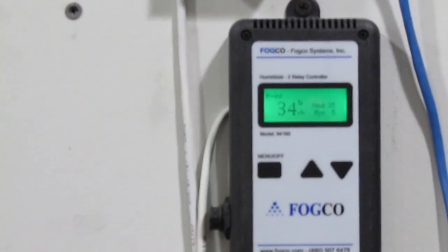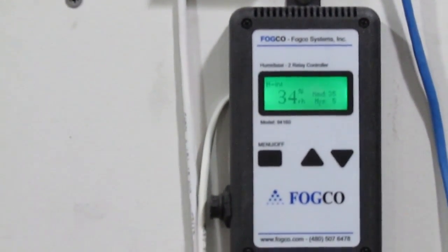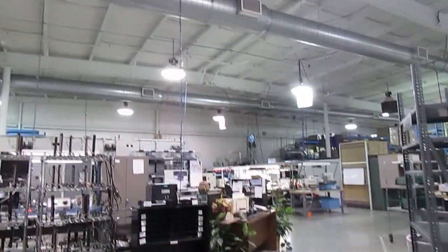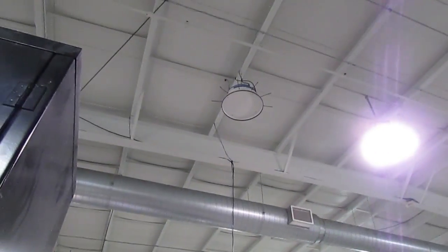The IPC standard is 30% to 70%. Here in western New York, where the winter air is quite dry, we need to use a humidity control system.